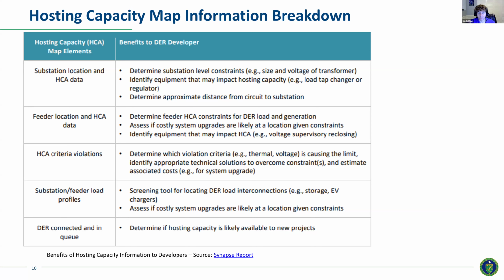Other valuable information isn't just the resulting calculation - like there's 4 megawatts of hosting capacity - but which criteria were evaluated and at what level violations started to occur. So if I see 4 megawatts of hosting capacity because of an anti-islanding requirement, but the next level up is 9 megawatts, then if I pay for that anti-islanding upgrade I can get quite a bit more equipment size. If the next one up is only 0.5 megawatts, it may not make sense, or I may want to size accordingly. Knowing at what level these constraints are violated helps you pick the right system size when you apply.